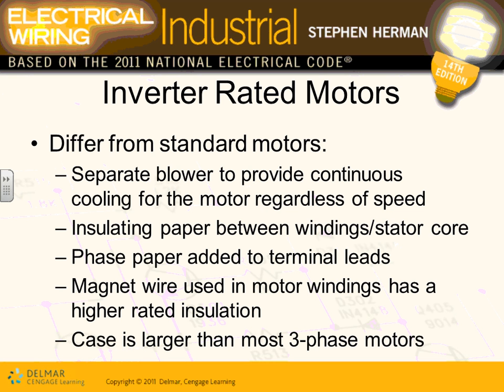So if the VFD is operating at the same current and the same horsepower, it's going to cause more heat. When you reduce the voltage, and in turn you reduce the frequency, some drives maintain the torque, others actually reduce the torque too, control the torque. That altering, instead of just letting the motor run at whatever horsepower, speed and torque it is designed for, which lets the motor run based on its rating. Now we start altering the torque, the voltage, the frequency, and the current. It creates stress in the motor, in the form of insulation stress and in the form of voltage spikes. So if you insulate the system better, you can handle the spikes in the voltage, meaning you're not going to damage the insulation and short.